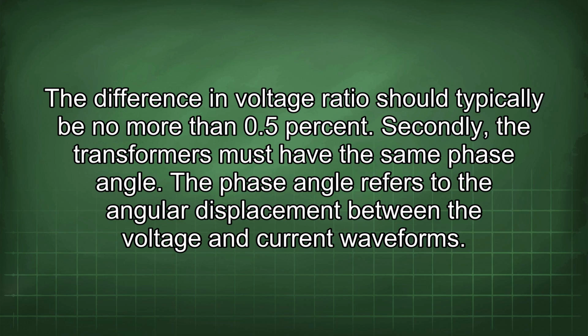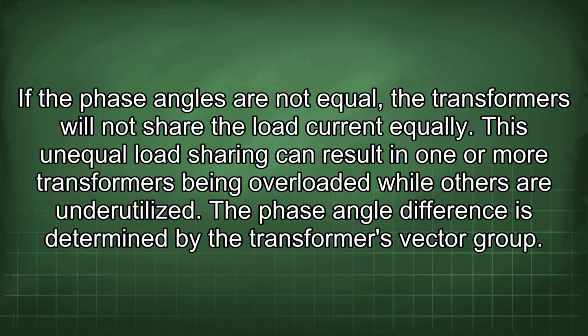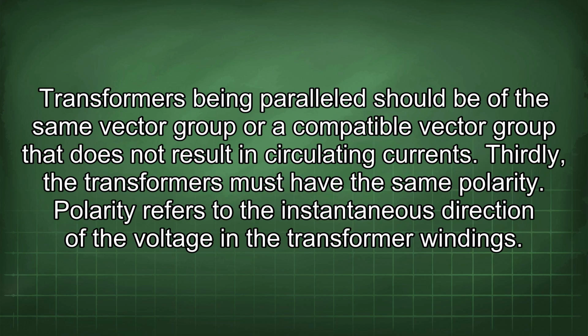Secondly, the transformers must have the same phase angle. The phase angle refers to the angular displacement between the voltage and current waveforms. If the phase angles are not equal, the transformers will not share the load current equally. This unequal load sharing can result in one or more transformers being overloaded while others are underutilized. The phase angle difference is determined by the transformer's vector group. Transformers being paralleled should be of the same vector group or a compatible vector group that does not result in circulating currents.